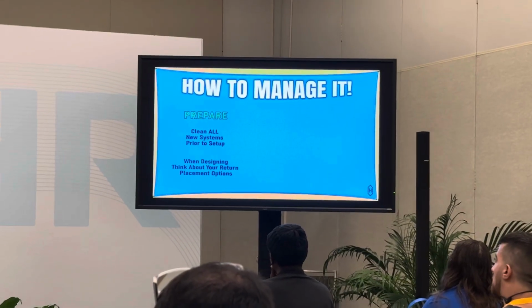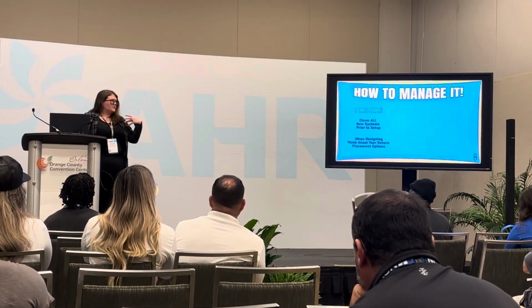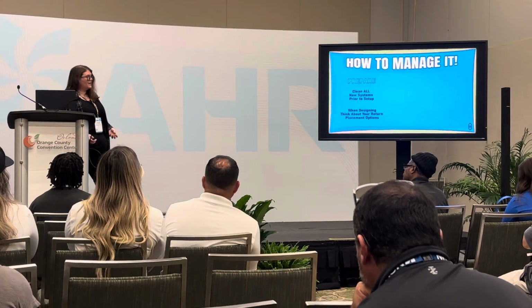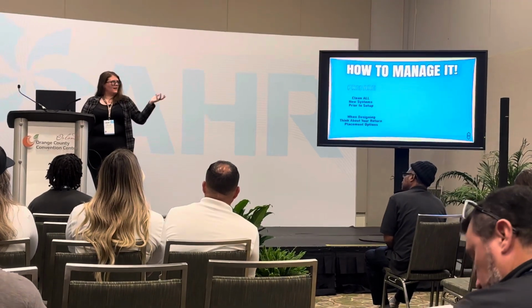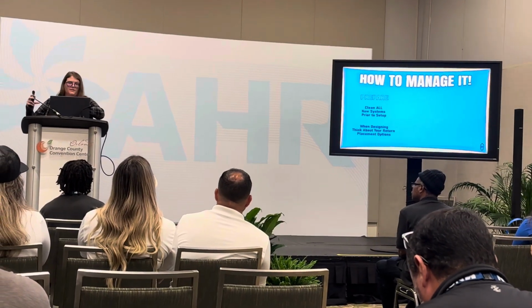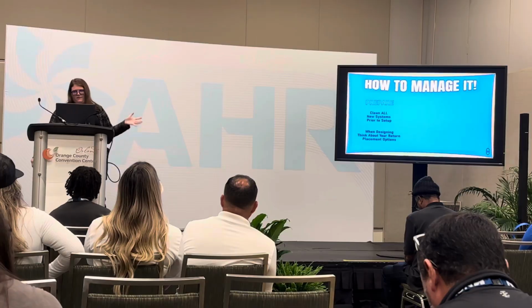Because what's happening is, I believe this is actually starting from the manufacturing systems and then coming into the home. Cause there's something about you dragging this into your house on your shoes, since you live in Florida and stuff like that, that soil bacterium is in your environment. You're bringing that dirt into your house and then the air handler's sucking it up, but I just don't see that growth that fast. So I highly, highly think that these are actually lying dormant on the coils themselves. And then when you go in there and you set up a system and you turn it on and that water starts, it just blows up, because water gives life.